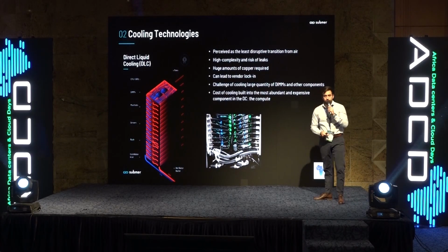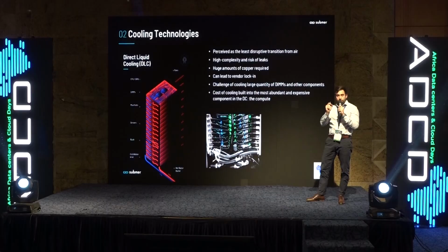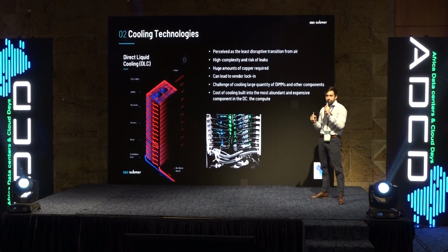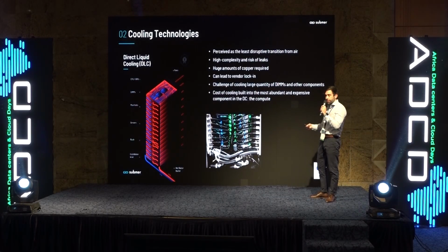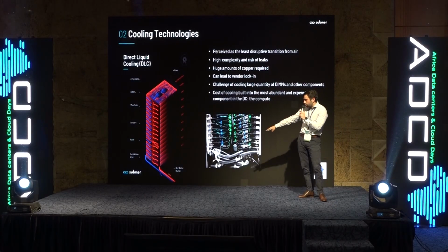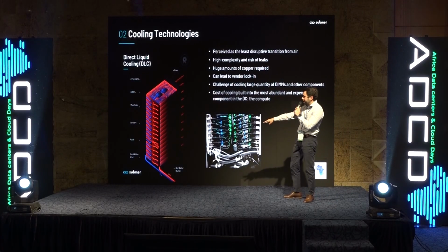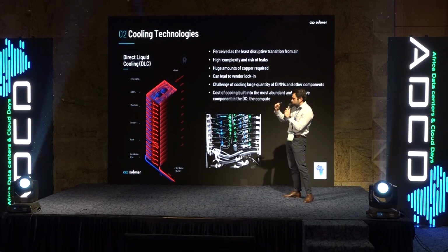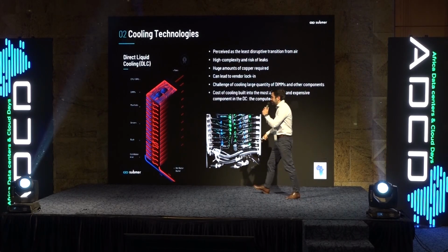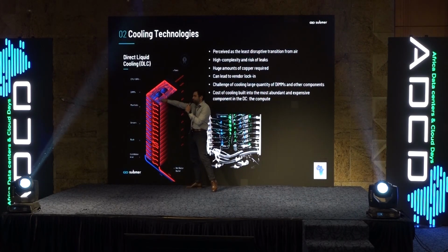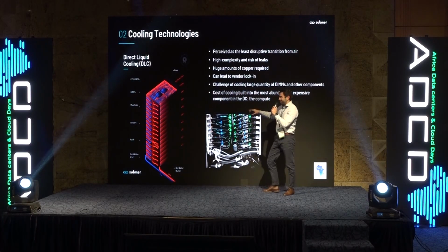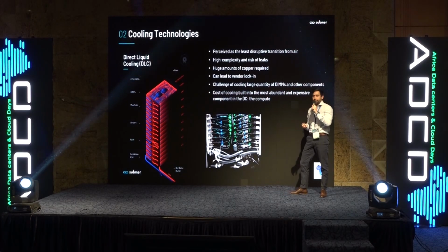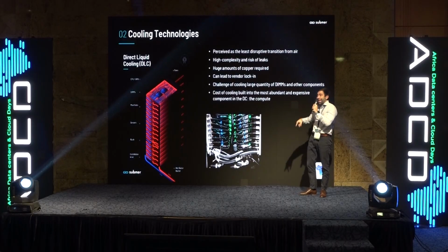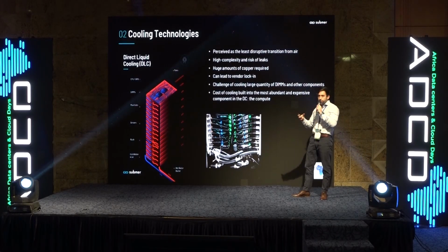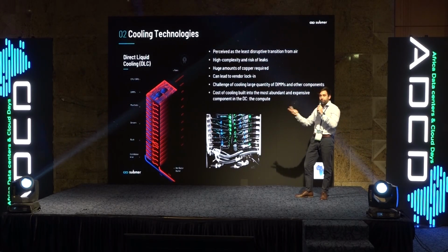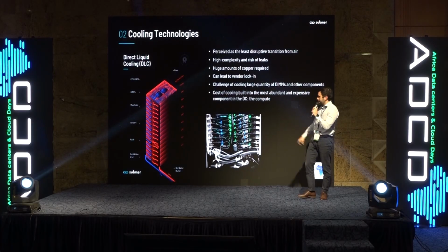Direct liquid cooling, or DLC, focuses on the component generating the most heat in the server, the chip, CPU or GPU. They bring a cold water loop through a manifold connected to small pipes that go to the servers and dissipate the heat of the CPU and GPU. That's about 70% of the total heat in your server. The other 30% requires another water loop to generate cold air to dissipate the rest, so you end up with two different water loops in this solution.